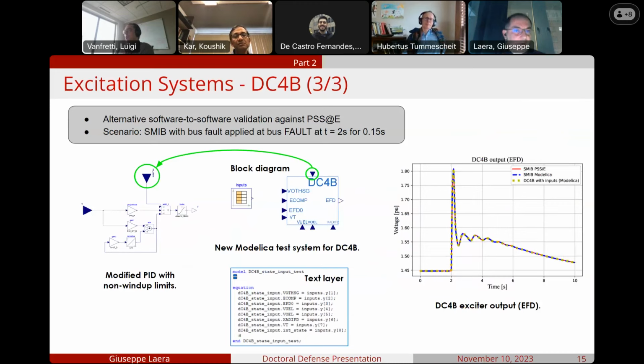An alternative approach for the validation of this component is offered by Modelica. It consists of simulating only the block represented from the DC4B exciter system, driven by external input signals that are collected from an SMIB reference in PSSE and saved into this lookup table.